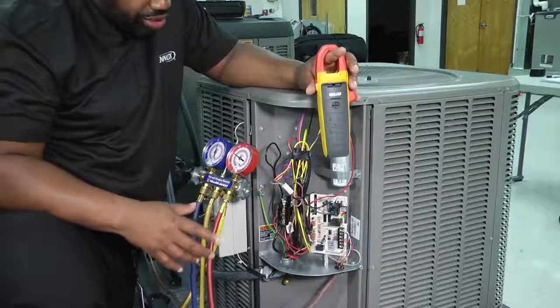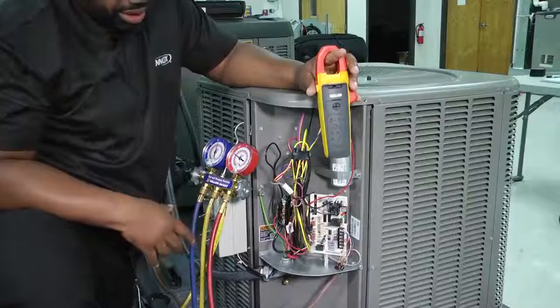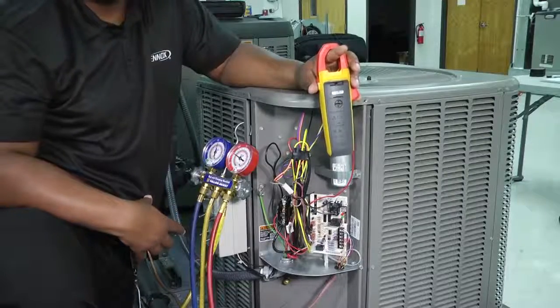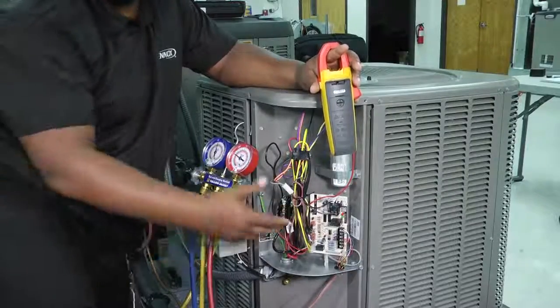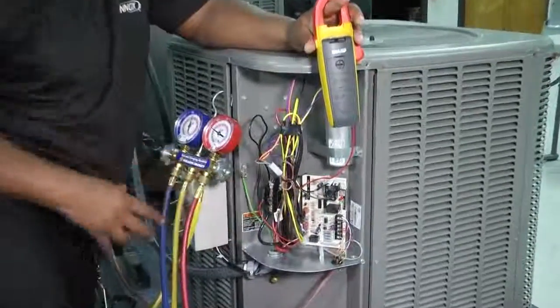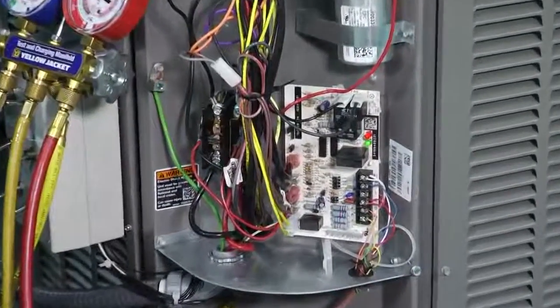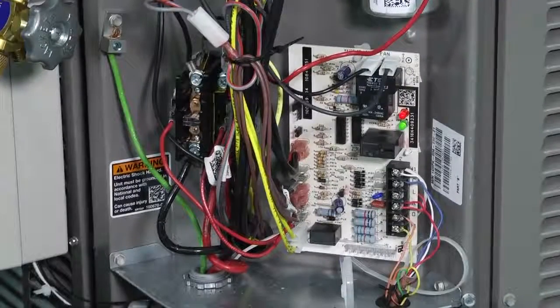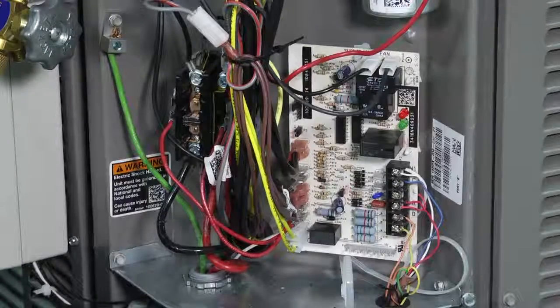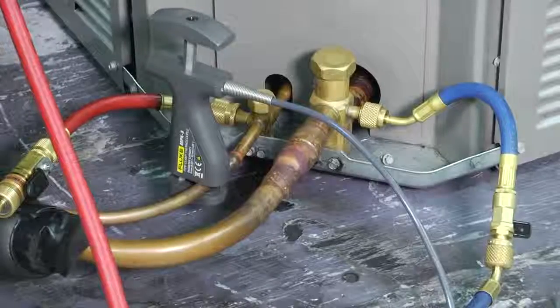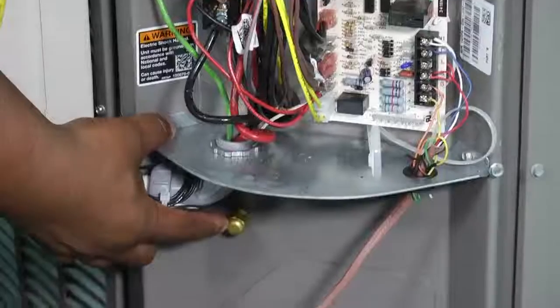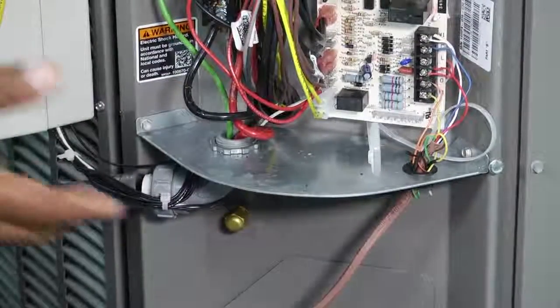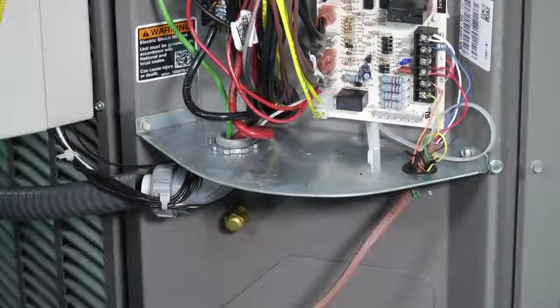So the other thing is, you'll notice that we have a circuit board in here because this is a heat pump system. So there's some test pins and some defrost mechanisms that you could test on your board to make sure your defrost cycle works properly on your heat pump, and also make sure that you connect on your heat pump to the true suction port, not necessarily the suction port, but the true suction port located on the systems. So you'll notice right up under here, there is our true suction port for our heat pump. So if we were checking it in heat pump mode, we want to make sure that we hook up to the right place.